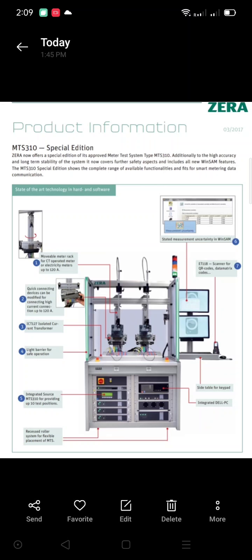That means association and data read of this energy meter with the communicating devices. The associated test system software has the facility to check the correct association of all connected smart meters on the meter test bench. Regarding the data read, the associated test system software has the facility for selecting any 5 or more readouts from the instantaneous parameters listed in the table of IS 15959 Part 2. The user can select or deselect the parameters randomly based on their requirement. So easily the data can be read, as our test system has a facility to read the instantaneous data from the smart meter. So the communication can be tested.